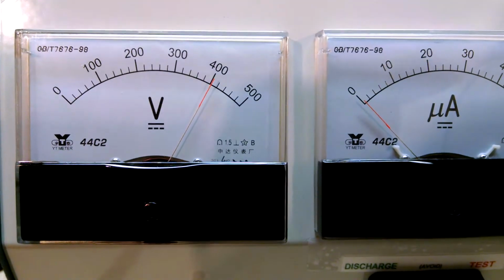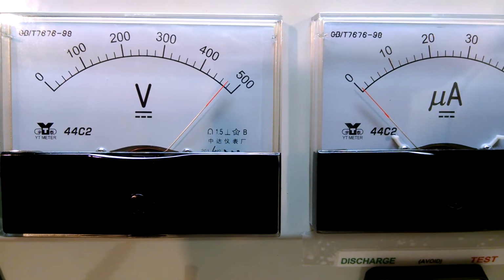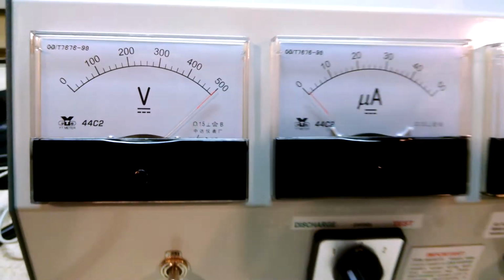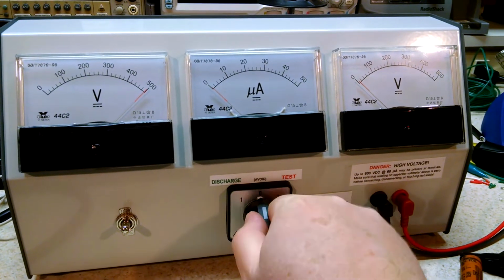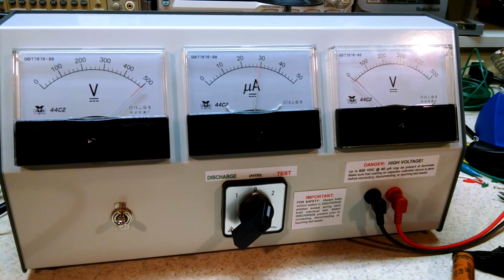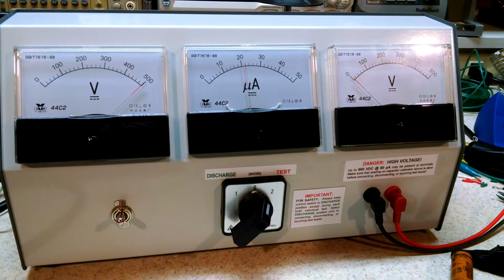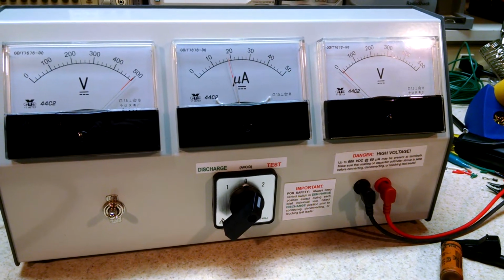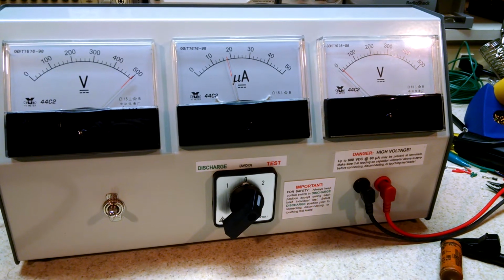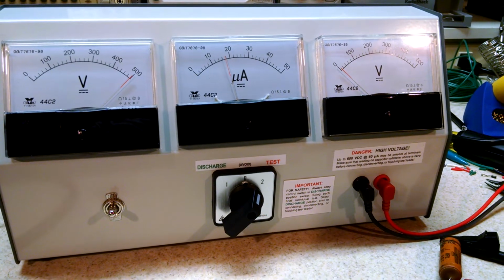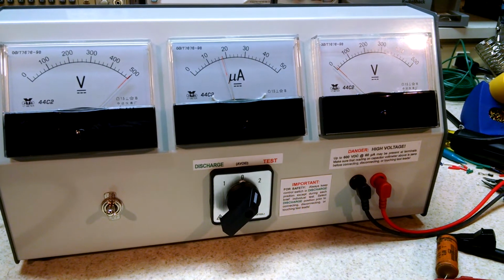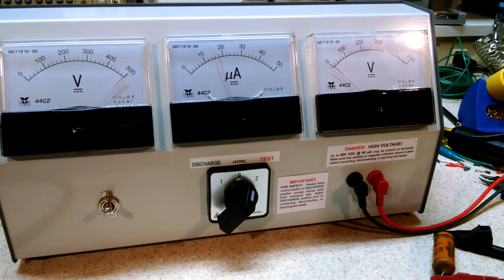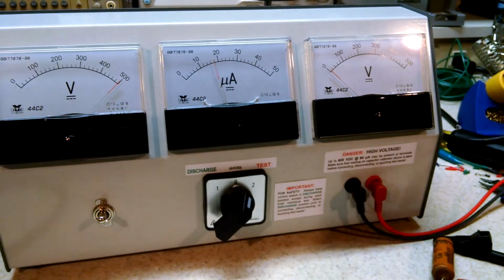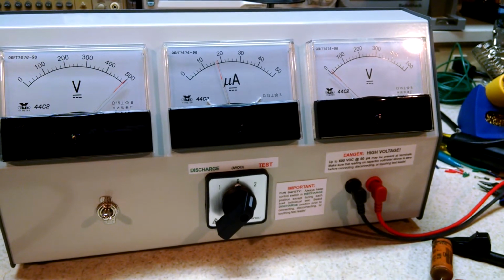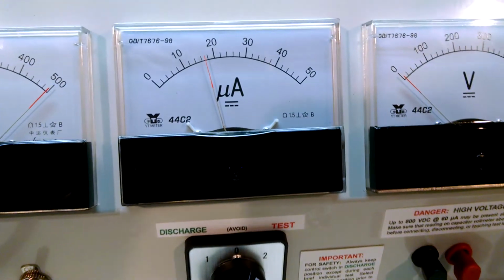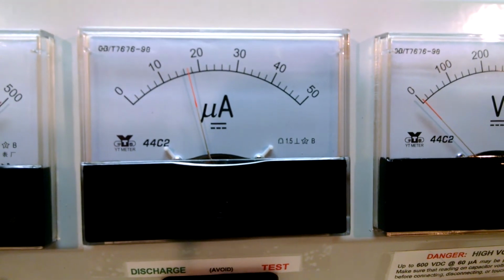We'll go down and adjust the voltage up to 500 volts, the maximum that this equipment is designed to handle. So we can see that as the capacitor is rated for 600 volts, we're applying 500 volts, which is pretty close to full working voltage, and we're still showing about 18 microamps of current. 17, 18 microamperes of leakage current.